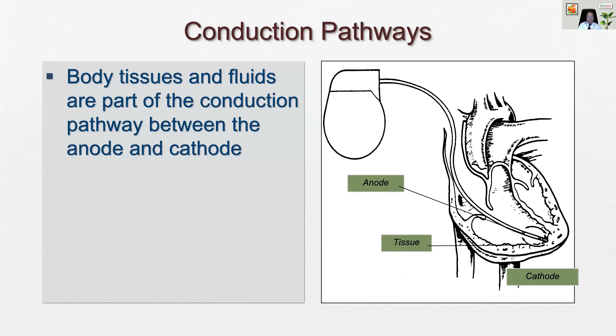Now, a unipolar system, as I said, has only one electrode at the tip, which is the cathode, and the lead has only one conductor, and the pacemaker body functions as the anode. So the electrical current starts in the pacemaker, goes through the lead into the heart, and comes back through the body into the pacemaker. So the pacemaker body works as an anode.